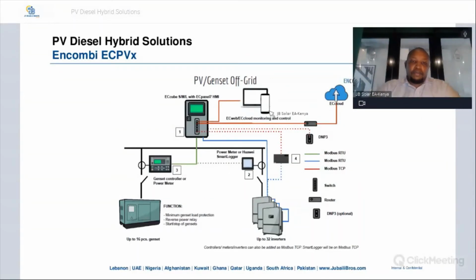And this is a line diagram of how the fuel save controller can work with the PV and generator in off-grid settings. One thing to note is that one hybrid or one fuel save controller can work with up to 16 generators and up to 32 inverters. So it is not dependent on capacity, but on the number of generators and inverters you have. Regardless of your installed capacity, it will work with up to 16 generators and up to 32 inverters.